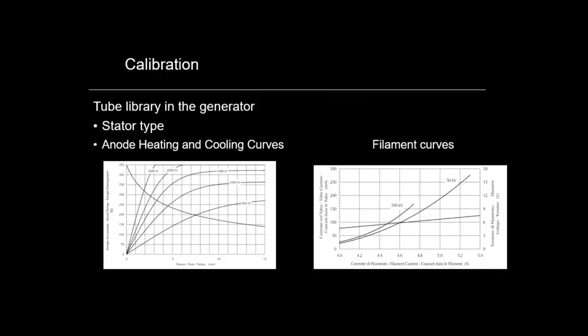Okay, so in the installation, there's a calibration. A product data sheet comes with the tube, and you have anode heating and cooling curves, and you also have the filament. It's important that the engineer note these and make sure he calibrates the system. A lot of systems now have automatic calibration, so you put the tube in, as long as the tube is compatible, it will assume these curves and run through the calibration itself and define the curves.